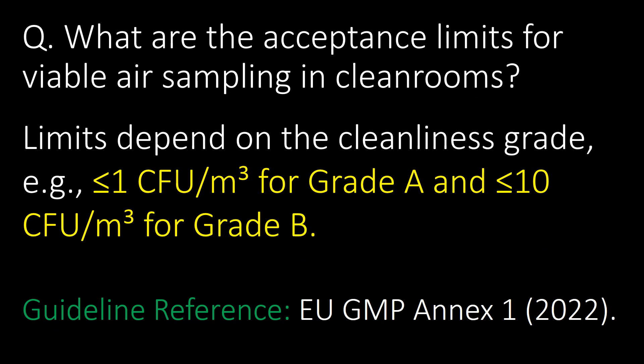Very important question: what are the acceptance limits for viable air sampling in clean rooms? Limits depend on the cleanliness grade. For example, less than 1 CFU per cubic meter for Grade A and less than 10 CFU per cubic meter for Grade B. Guideline reference: GMP Annex 1.